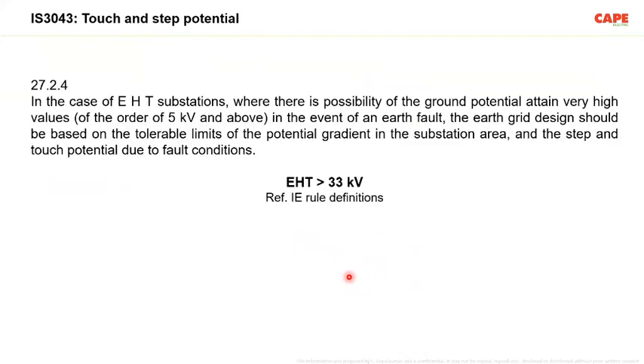IS 3043, clause number 27.2.4, very clearly states: in the case of an EHT substation where there is a possibility of ground potential attaining very high values, of the order of 5 kV and above, in the event of an earth fault, the earth grid design should be based on the tolerable limit of potential gradient in the substation area and the step and touch potential due to fault condition. So basically, this clause says you must implement these touch and step voltage safety measures for EHT substations, meaning above 33 kV.